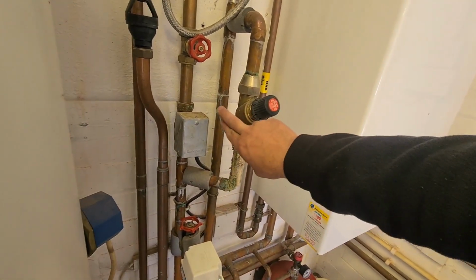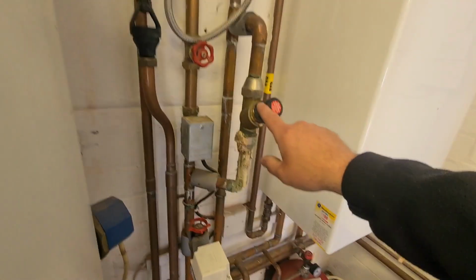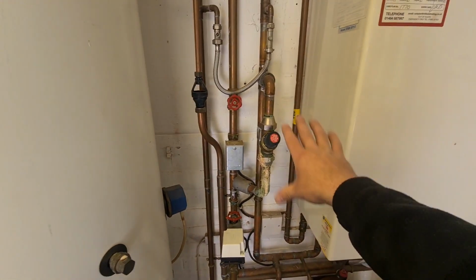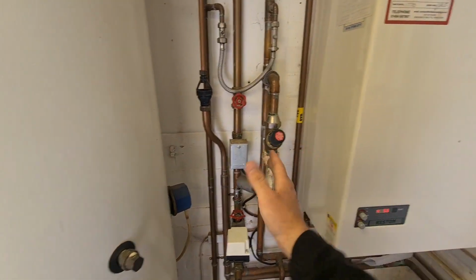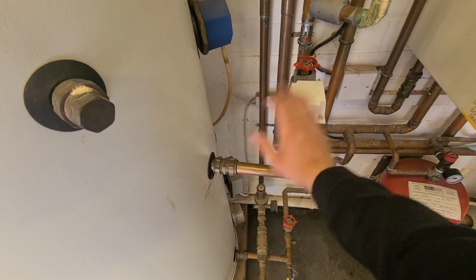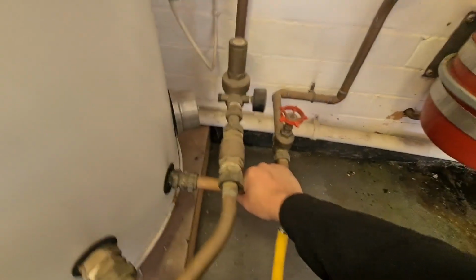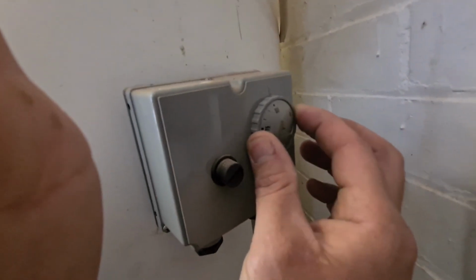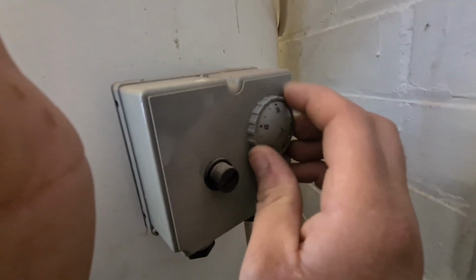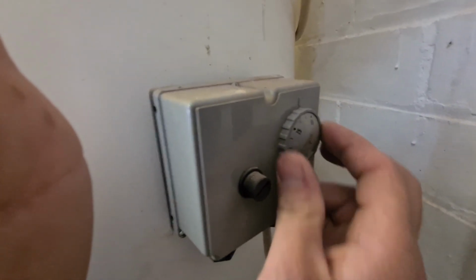This valve here has collapsed inside, so it's allowing a full flow. So it's taking its easy circuit around the system basically now. It's not forcing it on the cylinder, because my hot water's been in demand for days now. That is boiling hot. The return's stone cold, and you'll see on my cylinder stat here as well, going all the way down to 30 is not even turning off, it's not clicking, so that tells me the bottom half of this is not even warm, and it is lukewarm up there.